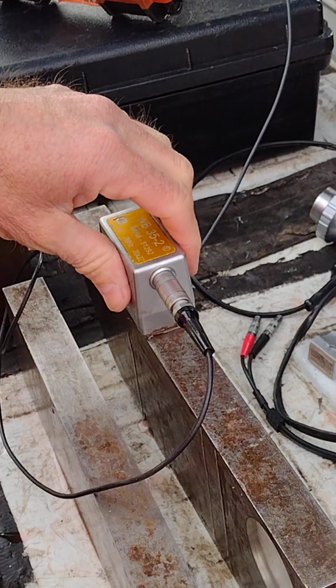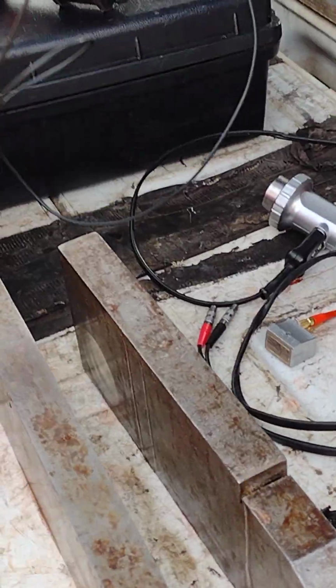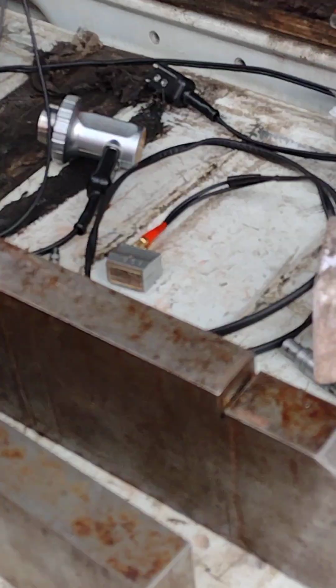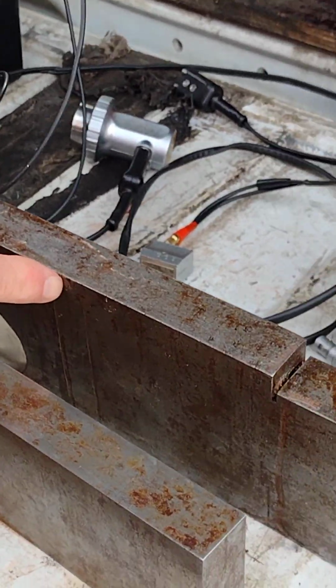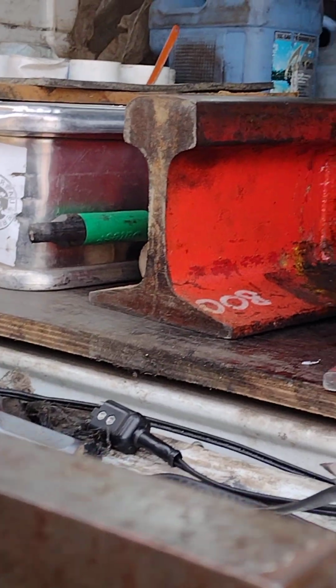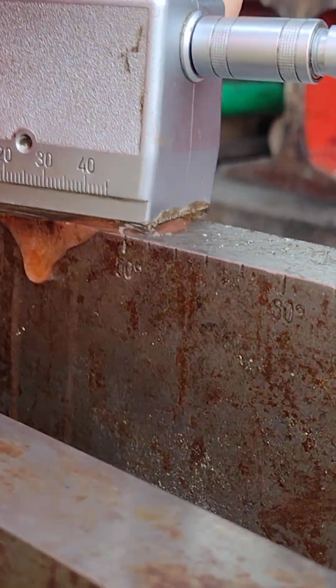We're going to check our actual probe angle. So we're going to flip the block over on this one because we've got a 38 degree probe. We've got a scale 35, 40, 45, 50.